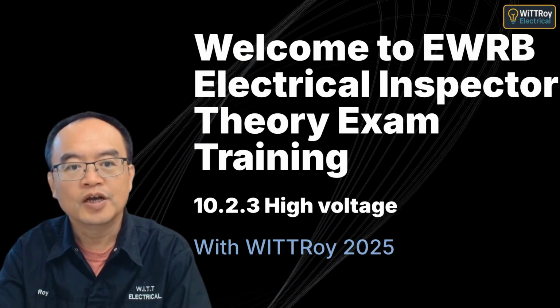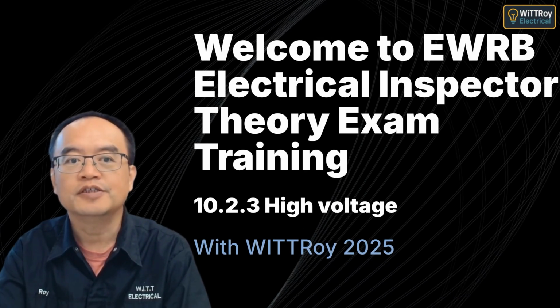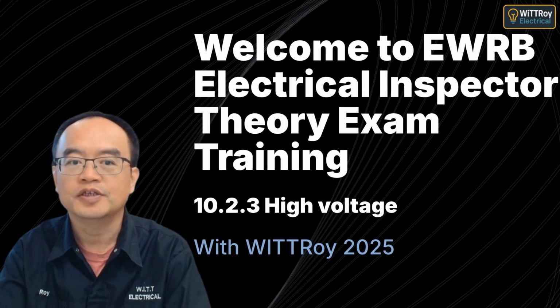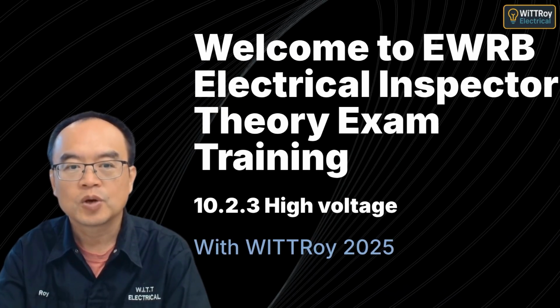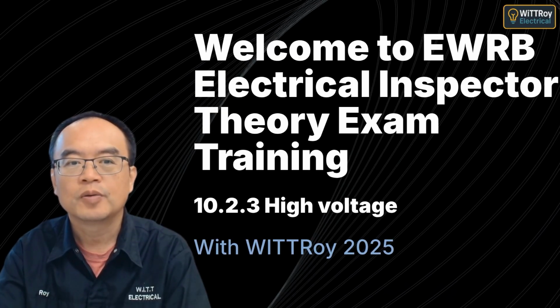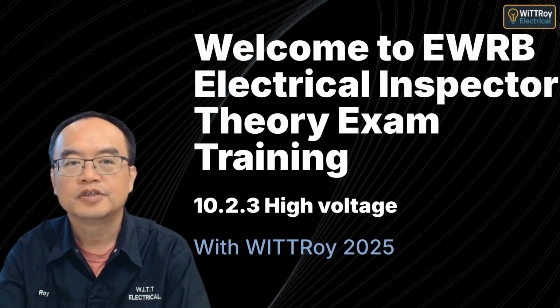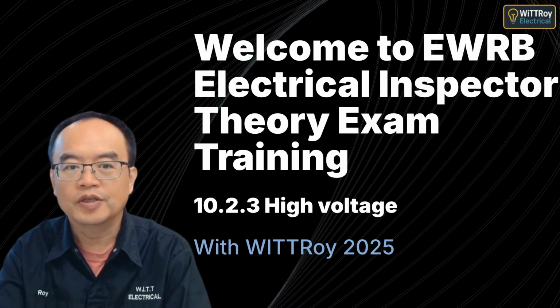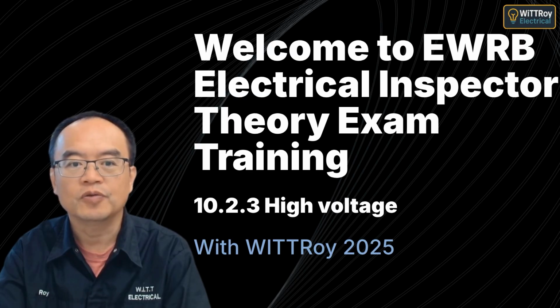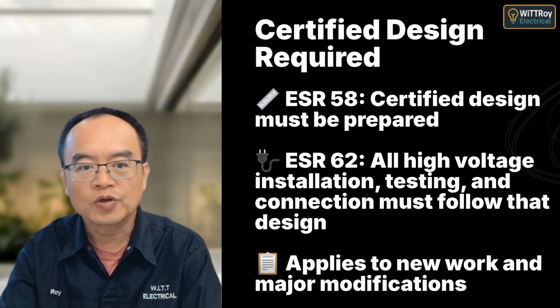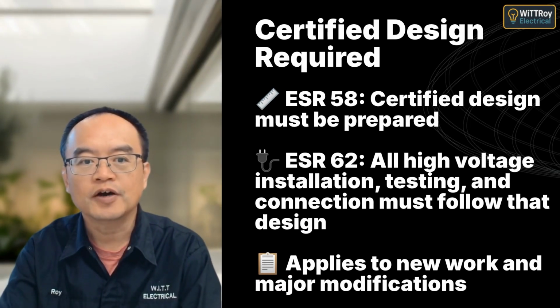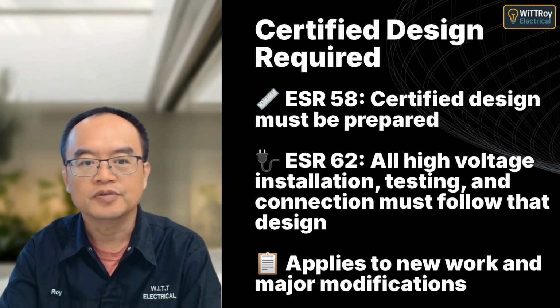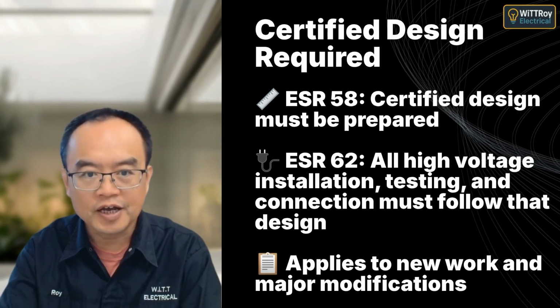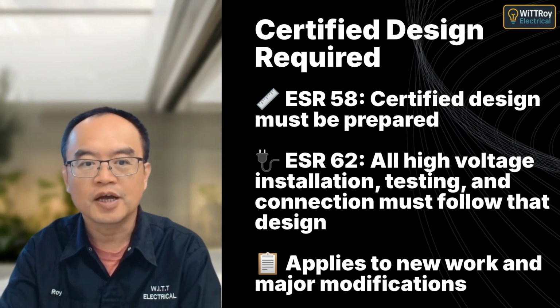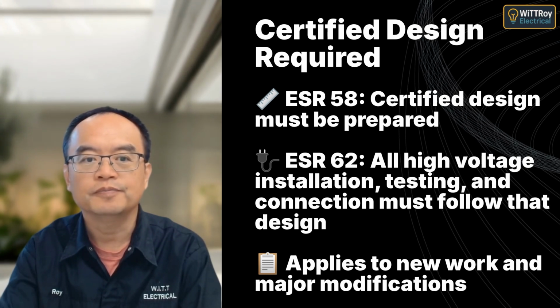In this short lesson we're covering 10.2.3 high voltage installations. We'll go through the key certification and inspection requirements and the risks that come with testing and working on high voltage systems, all aligned with the electricity safety regulations and NZECP 34. According to ESR 58 and 62, high voltage work must be based on a certified design. That design guides the installation, testing, and connection and must be available on site.